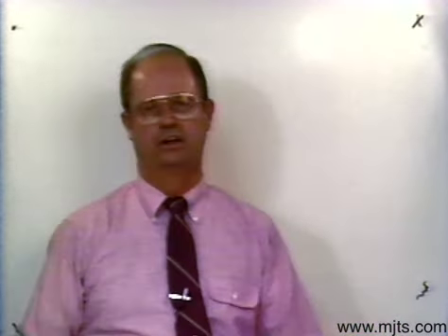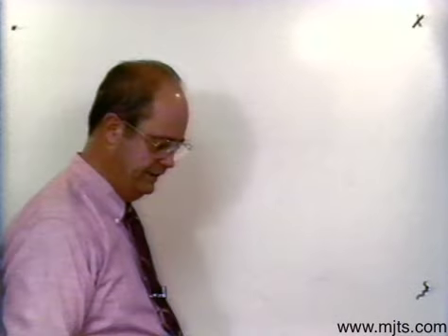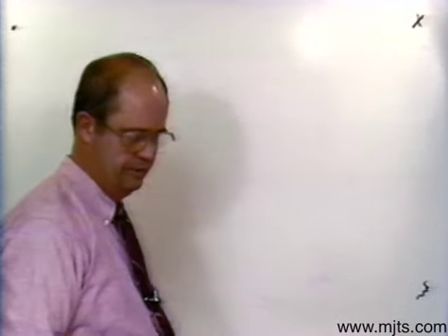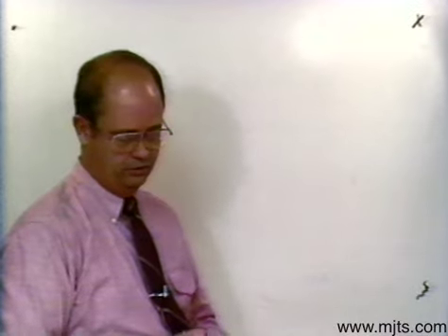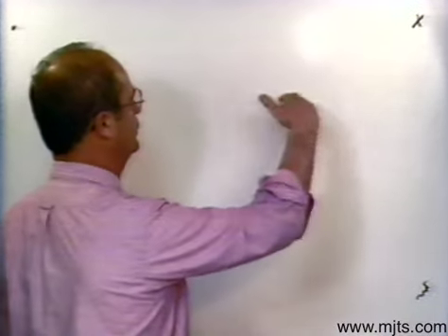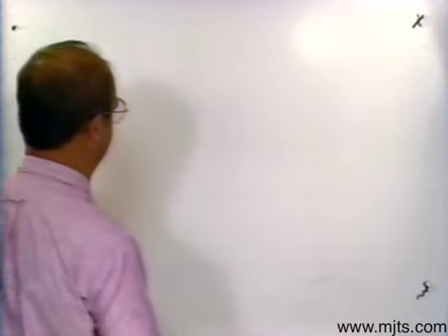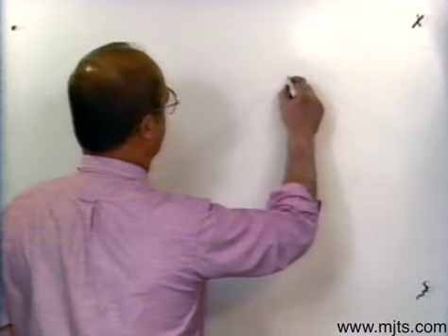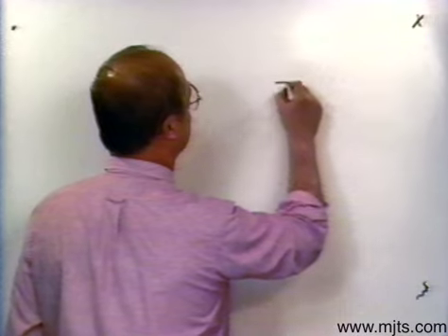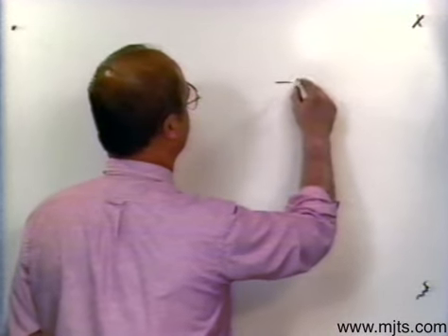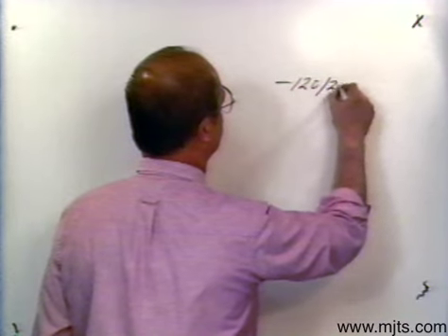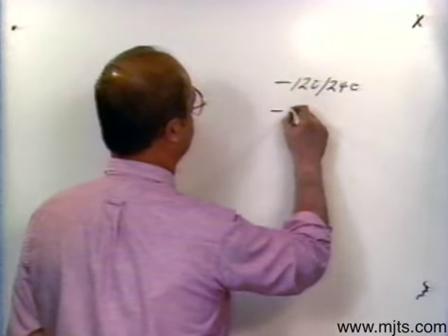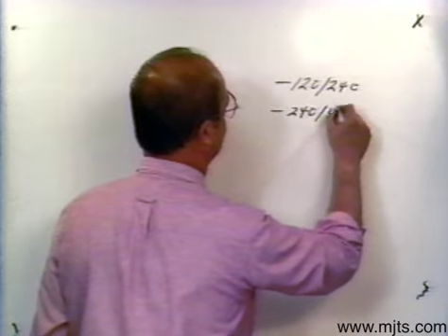Now let's go through our low side windings. We have different ways of writing and indicating our low side ratings. Remember the hyphen we had before that denoted a separate winding. The most common, if I were to draw it out, would look like this: a hyphen denoting a separate winding, then 120/240 or hyphen 240/480.